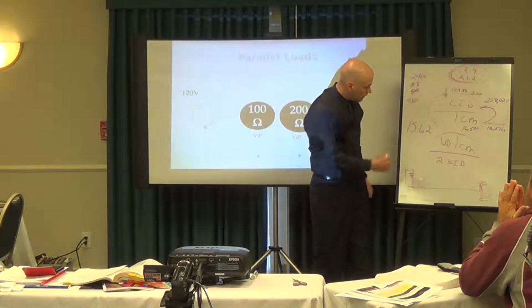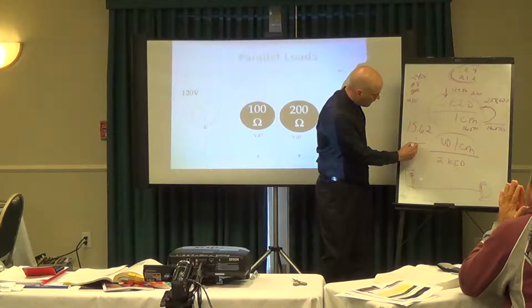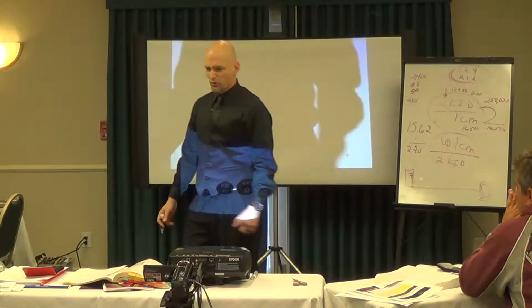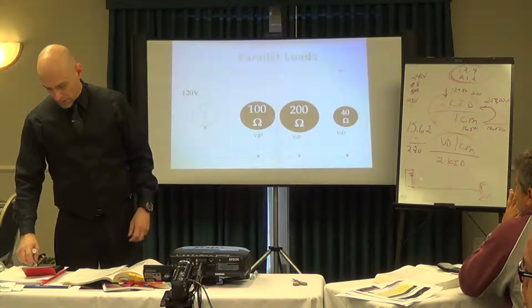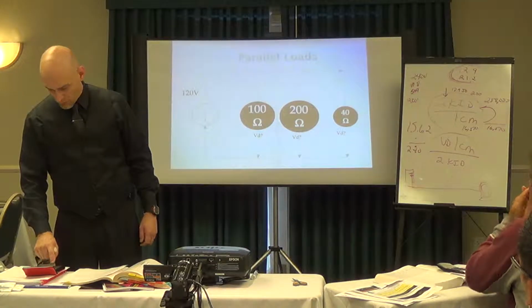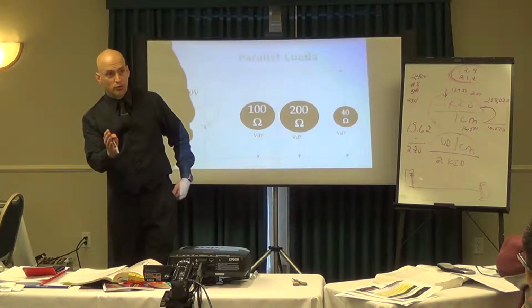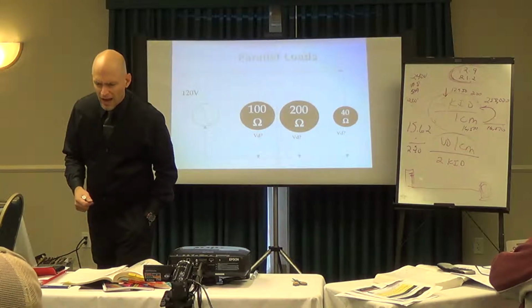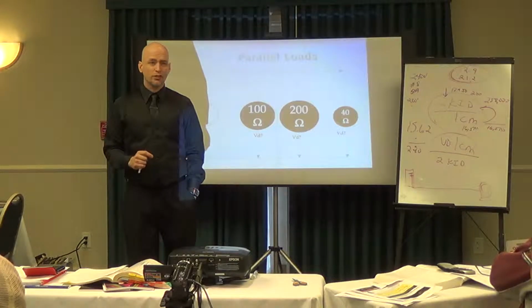So to convert that, you just hit the division sign on your calculator, divide it by the system voltage of 240 volts, and what do you have? 0.0 something? 0.065. And then to convert that to percentage with the decimal in 2 places, you get 6.5%, which is a little too much.